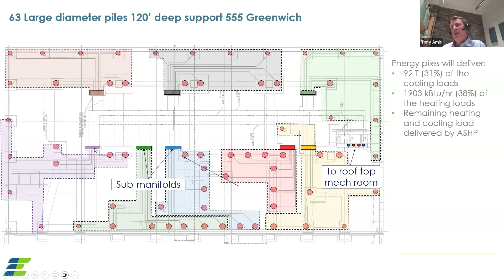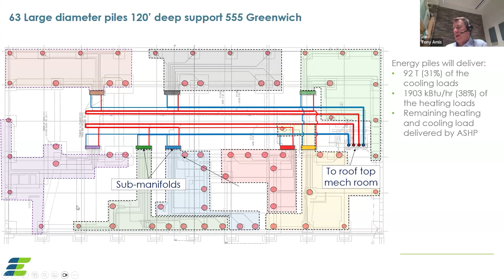We put 3 geothermal loops in each pile, connected in series and run back to a submanifold, so if there was an issue later we could isolate it. Each submanifold is then connected to what we call a reverse return system, which ensures the pile closest to the main manifold has exactly the same loop distance as piles further away. It's very important to get the balance right, and flow rates right, to ensure a nicely balanced system.